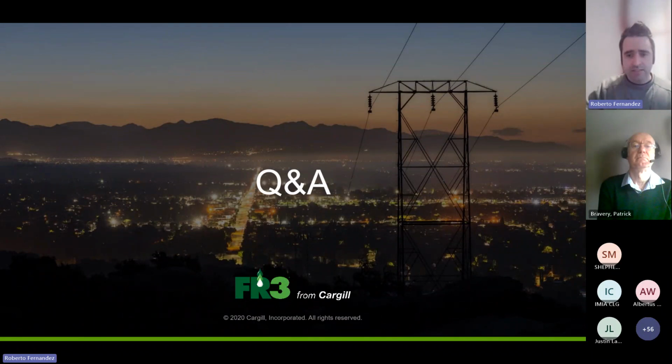And this puts some additional concerns on how to implement natural esters in very cold climates. I can share that there are natural ester filled transformers in all climates, and so far we haven't seen any big limitation here. So temperatures down to -25 are pretty straightforward. We have made a lot of tests, especially connected with renewable energy and wind farms, going down to -40 degrees, which is a very cold climate.